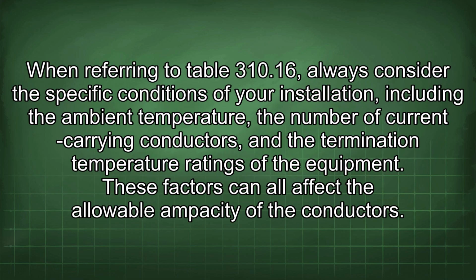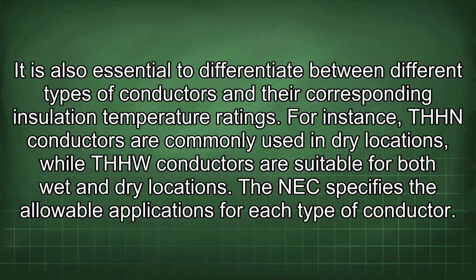When referring to Table 310.16, always consider the specific conditions of your installation, including the ambient temperature, the number of current-carrying conductors, and the termination temperature ratings of the equipment. These factors can all affect the allowable ampacity of the conductors. It is also essential to differentiate between different types of conductors and their corresponding insulation temperature ratings.